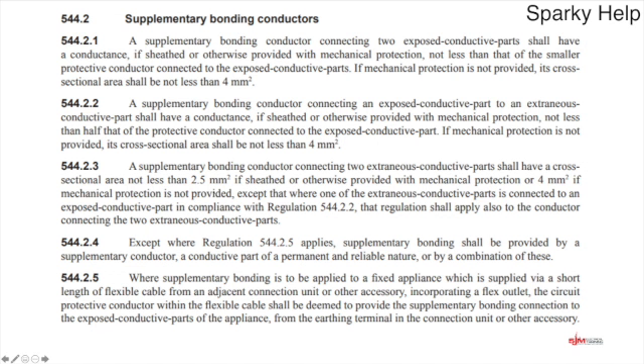Next one down, a supplementary bonding conductor connecting 2 extraneous conductive parts shall have a cross-sectional area not less than 2.5, if sheathed or otherwise provided with mechanical protection, or 4mm if mechanical protection is not provided. So that's a fairly common one. So supplementary bonding between 2 extraneous conductive parts, so that might be between your flow and return, or your hot and your cold, whatever it happens to be. And typically most people would probably put a 4mm in. However, I have heard people say they put 6mm in.